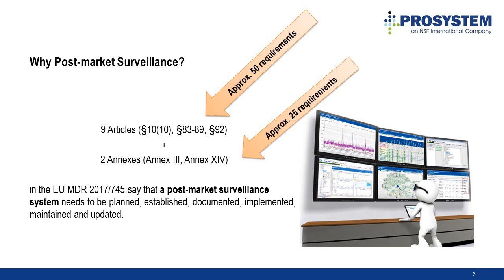This picks up the requirement of the ISO 13485-2016, where it also says that manufacturers should have documented procedures, which include provisions to gather data from production as well as post-production activities. While the standards stop there, the regulation picks up this requirement and provides further detail on the content and methodology of this system, as we will see on the following slides.